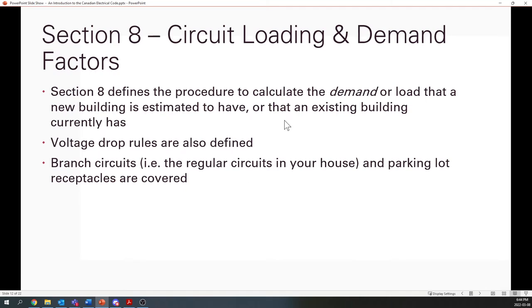Section 8 is circuit loading and demand factors. Section 8 defines a procedure so that you can calculate the kVA demand that a new building will exhibit when it's constructed, or you can use the dimensions of an existing building to calculate that as well.